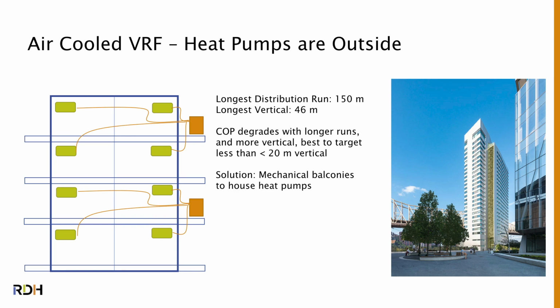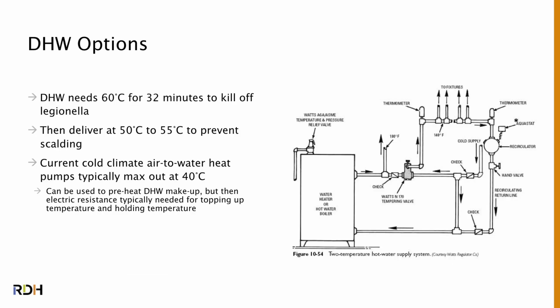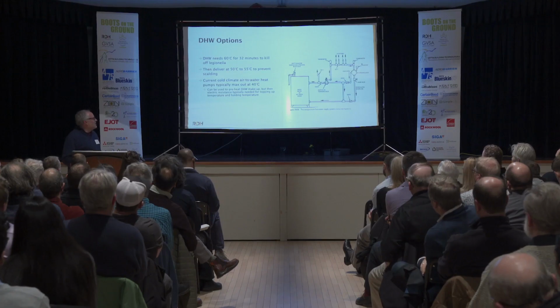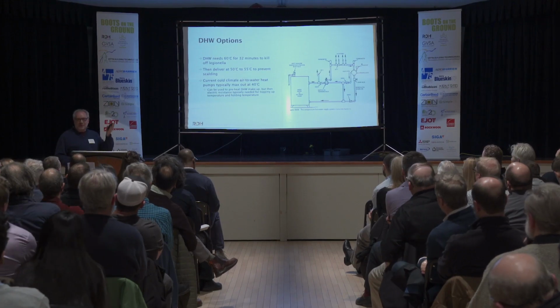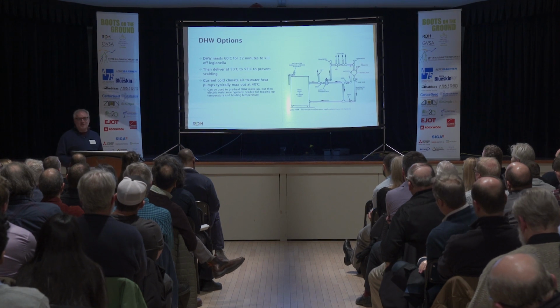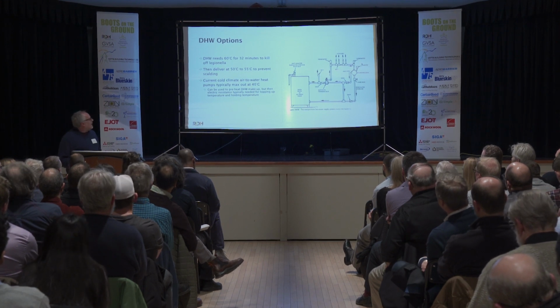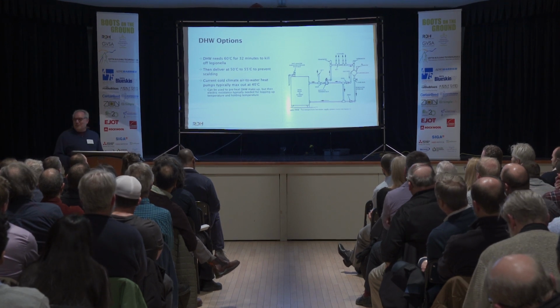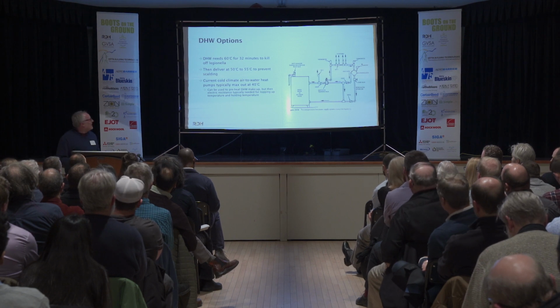Okay, domestic hot water. To kill Legionella, we need 60 degrees Celsius for 32 minutes. That's what kills it. Most of our air source heat pumps and water source heat pumps don't do 60 degrees Celsius, they do 40 degrees Celsius. Which means we're either preheating and then doing the rest with electricity, which means our standby losses are all electricity, which means it's actually a lot more electric resistance than you think it is.